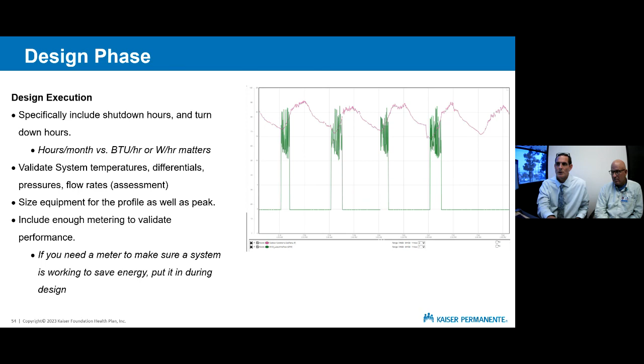And then, of course, commissioning—it wouldn't be a Kaiser FP&D podcast if we didn't talk about commissioning and validating all the measures. We have actually seen projects where our commissioning team is declaring success that really doesn't meet the measures we established. We've talked about that in some of our commissioning materials: when we set an acceptance criteria and don't meet it, please don't write a commissioning report that brushes that under the rug. That's time to raise your hand and have a larger conversation about the project goals and where the project actually wound up. And it's going to happen—it's going to continue to happen on projects.